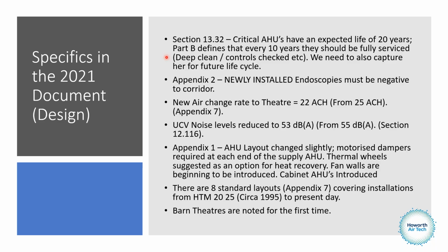So if we have a hospital that has 60, 70 air handling units in and it opens today, we need to capture when that's going to happen. So it might be in the 17th year we need to start replacing. Appendix 2 notes that newly installed endoscopies must be negative. There's a new air change rate from 25 to 22 air changes in operating theatres, and the noise level in UCV theatres matches that as well, 55 to 53.